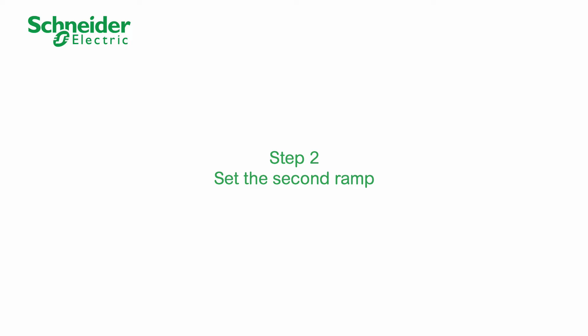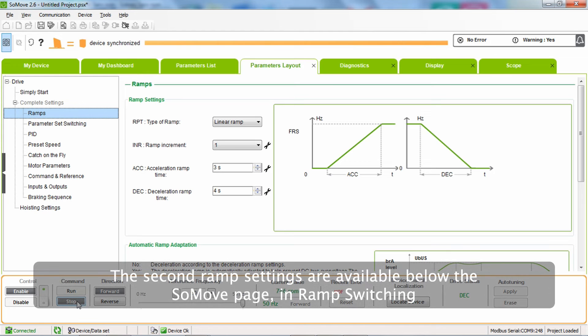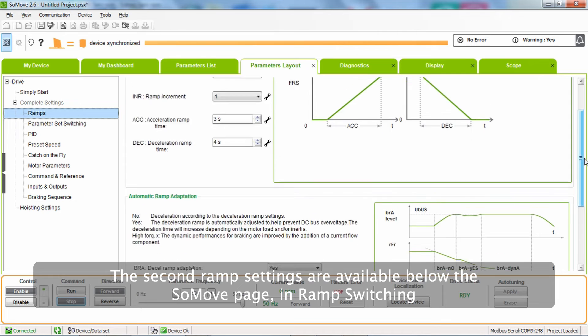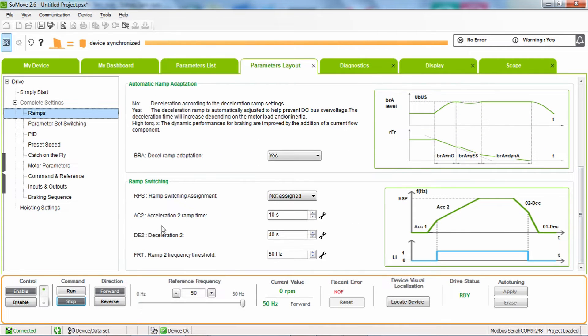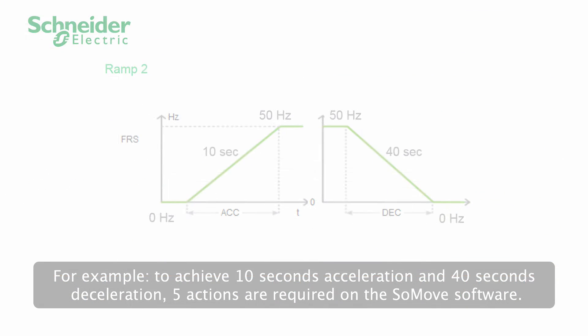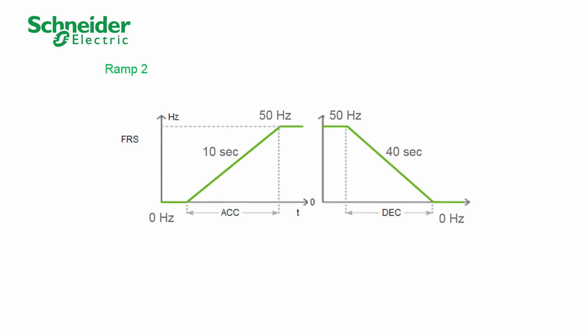Step 2. Set the second ramp. The second ramp settings are available below the SoMove page in ramp switching. For example, to achieve 10 seconds acceleration and 40 seconds deceleration, five actions are required on the SoMove software.